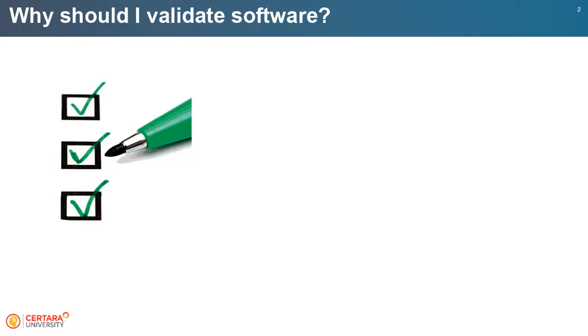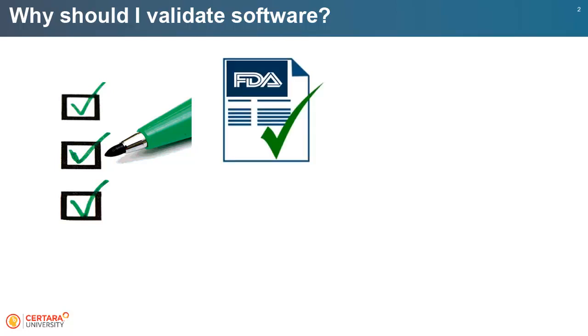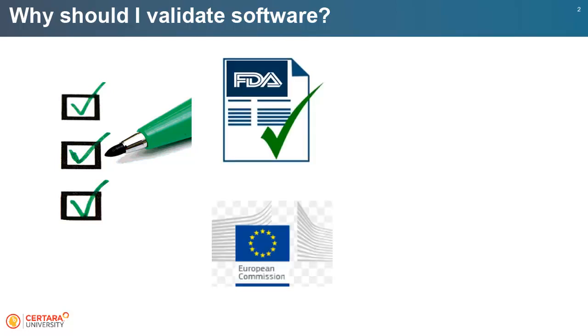Software validation requires investment of significant time and resources to manually write and perform the validation steps. Software validation requirements are described in several Regulatory Agency Guidance documents, including FDA 21 Code of Federal Regulations and EudraLex Annex 11.